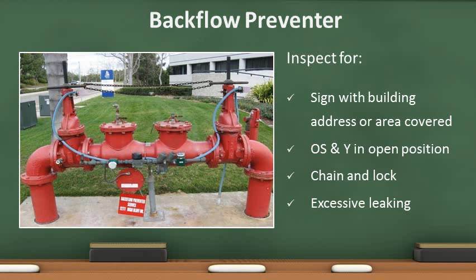Backflow preventers prevent water from flowing backwards into the street side supply. This one has an outside stem and yoke design, commonly called OS and Y. When the stem is outside, as in the picture, it indicates the valves are open. If the stem was not visible, it would indicate the valve is closed. There are two valves in case one fails. When properly installed, the stem valve is in the upright position. When conducting an inspection, look for excessive corrosion anywhere on the valve. The tamper switch and conduit should be intact and without damage.